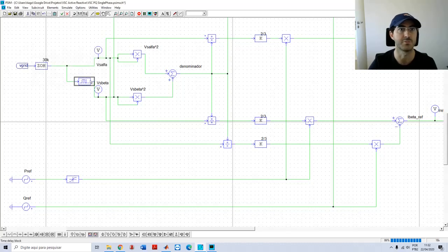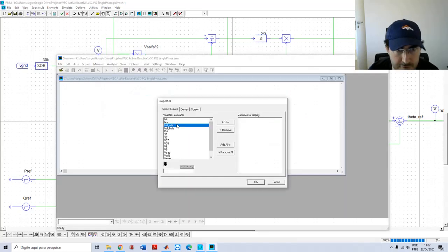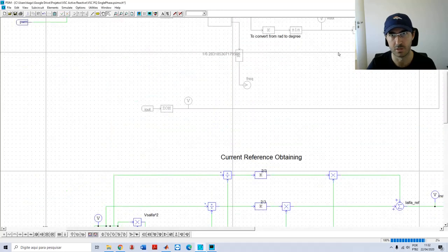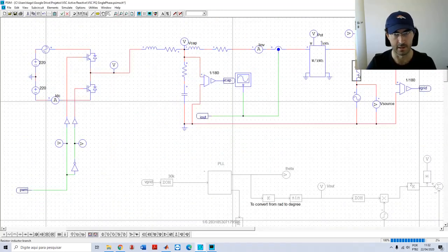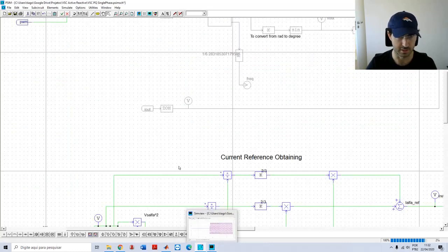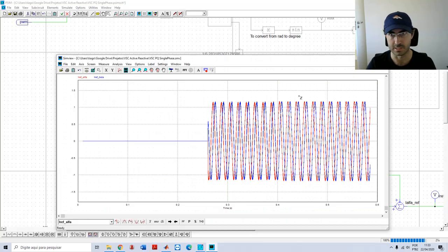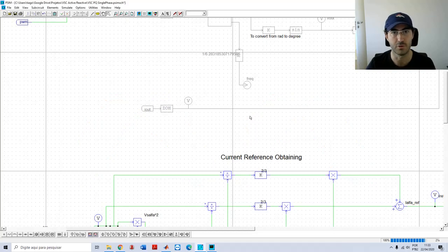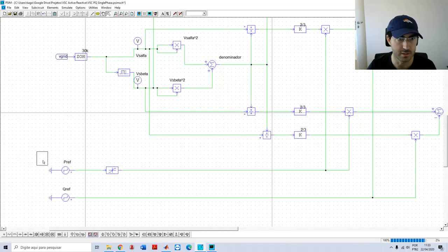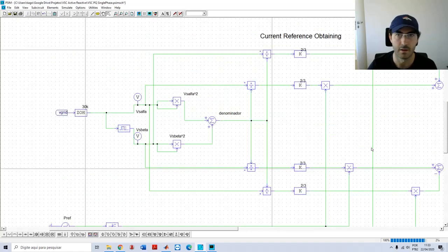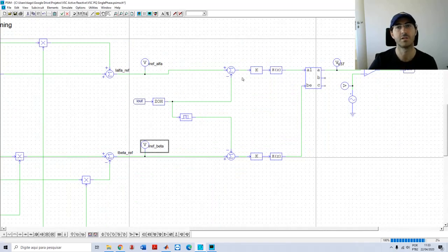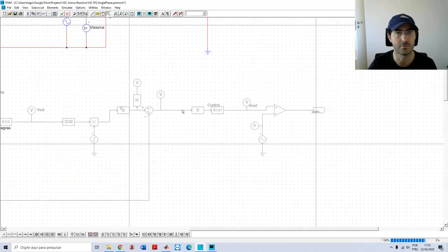This phase delay part takes more attention. If I look at the reference from Alpha-Beta, I have initially zero just to see the transformation later, and here is the reference for that. It is quite noisy because the voltage is quite noisy — I'm measuring the voltage at the PCC which has a line impedance. So it is natural that I have some noise but at an acceptable level. This is the reference that the controller must follow. You have P and Q references — still single-phase but now using Alpha-Beta. And since the references are obtained, I'm using the same controller I used in the single-phase ABC case, because that controller is able to follow sinusoidal references.